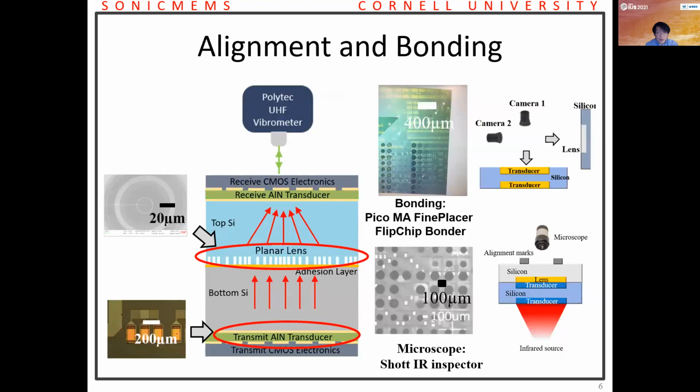This is the alignment and bonding. We use the PicoMA fine placer to bond the lens and the transducer, and we verify it using a microscope.